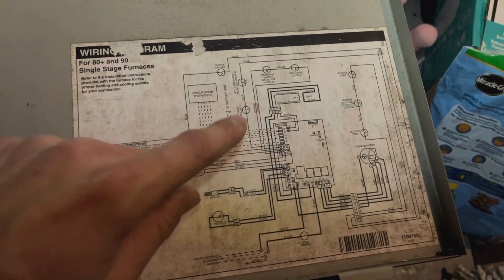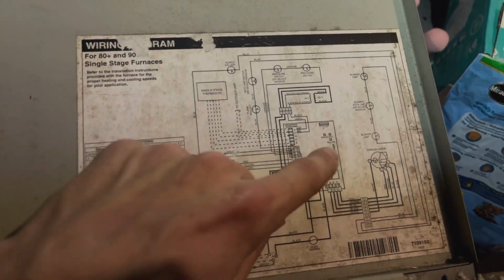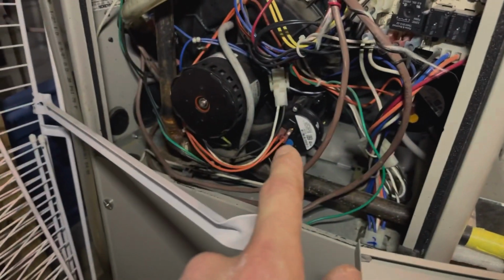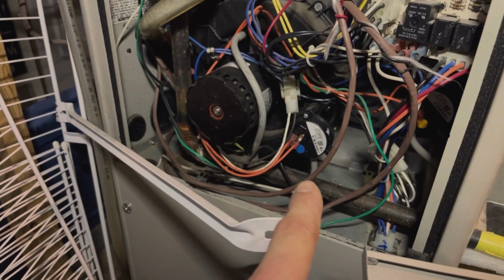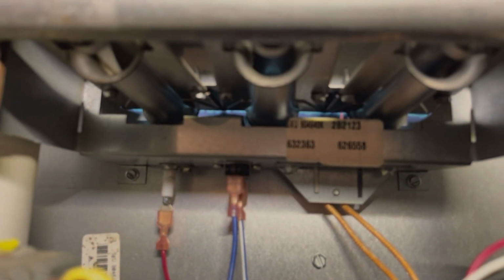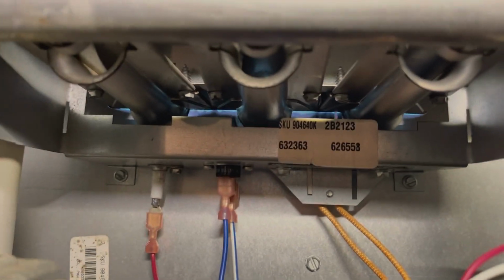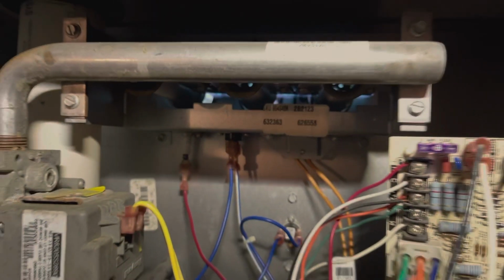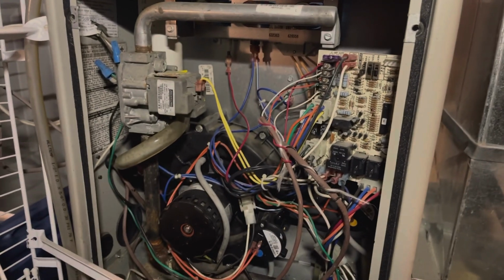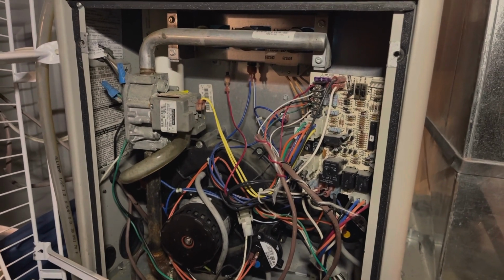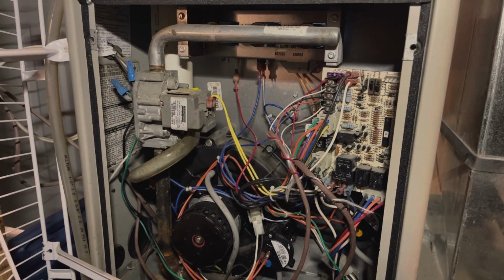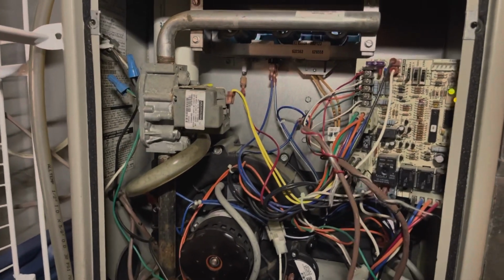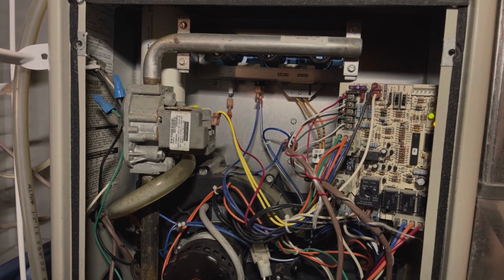And if you're having an issue with wiring things up, like I mentioned, your wiring diagram can be complicating, but if you're just removing one part, just look at the wires you're disconnecting and make sure you put them back in the same place. So I think that does it for how to troubleshoot and repair your furnace for a number of common issues you could have, as well as we explained the sequence of operation to some degree, so you can understand how your furnace works. Natural gas and propane are much similar, and you can dive into it a little bit and see if you can diagnose it yourself before you call a professional in too much.